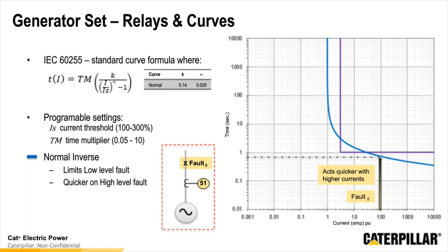Now, there's also value to the curve on the right side of the definite time or within that short time range. Typically, though, the generators in this case were showing that you would require 100 times the rated current of the unit, and it's very unlikely that a generator is going to be able to produce 100 times the rated current. But in this case, if it was, you would trip off slightly faster than what that definite time setting would be.